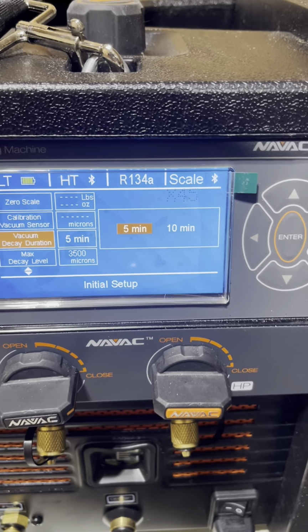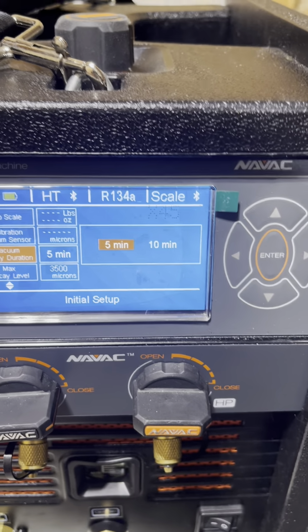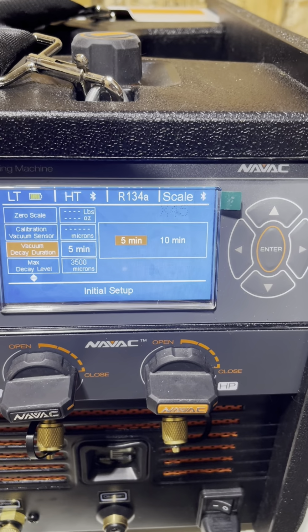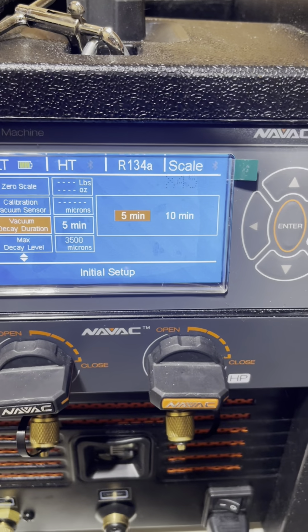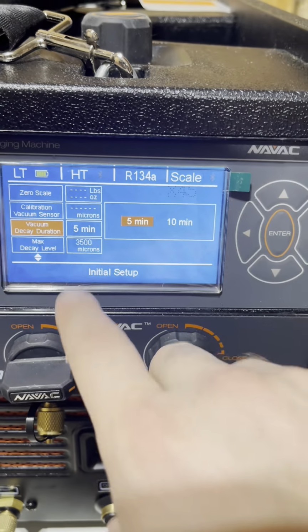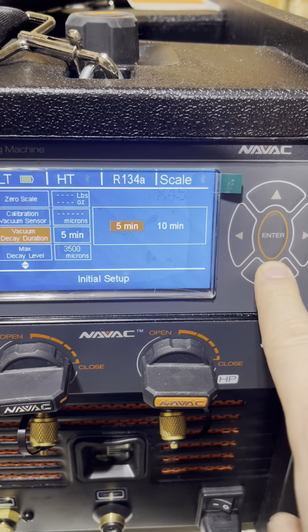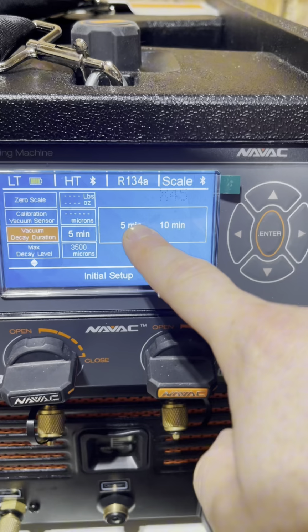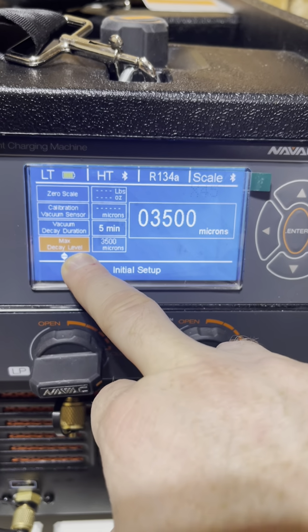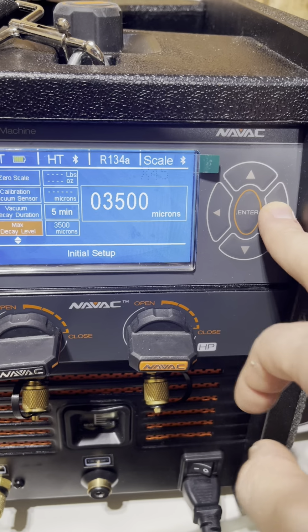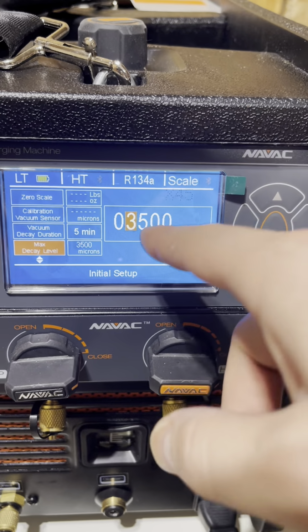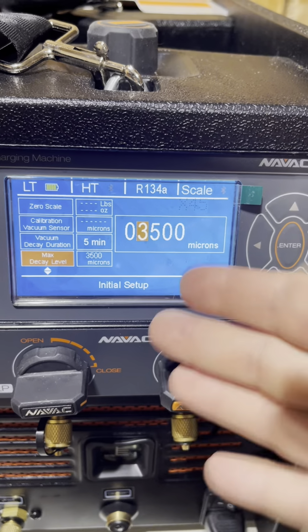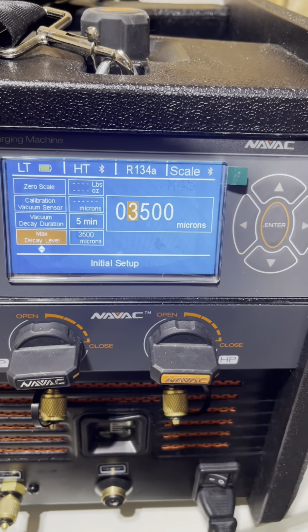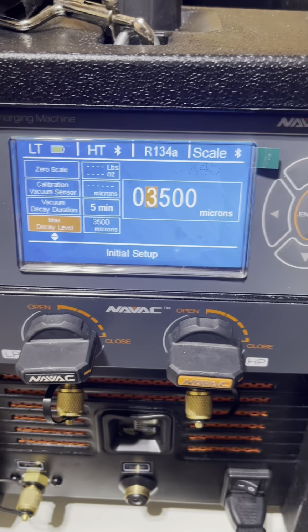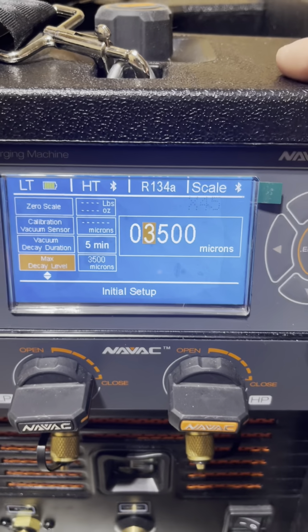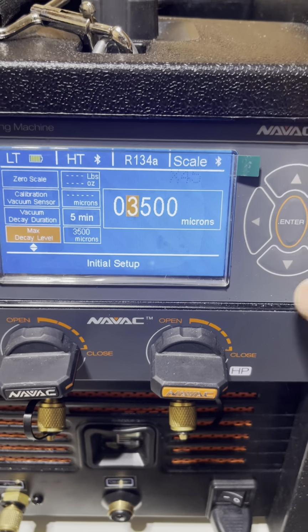when it reaches the desired vacuum, let's say 1000 or 500 microns, it will do the 5-minute leak test. And if within 5 minutes, you have to choose a maximum, I usually choose 5 minutes, and then you want to choose your decay level. I choose 3500. So if the pressure in my system rises above 3500, the machine will not go to the next stage, and it will not fill the system. You can play around with it.